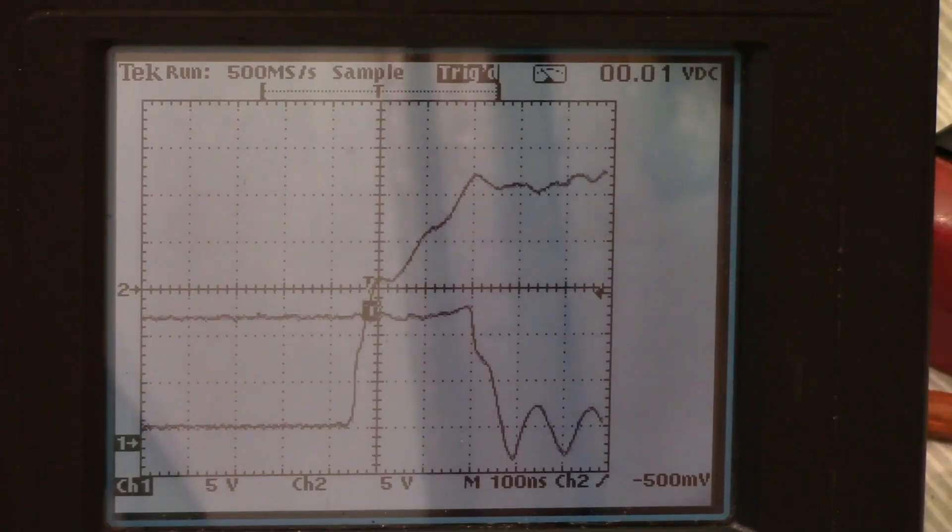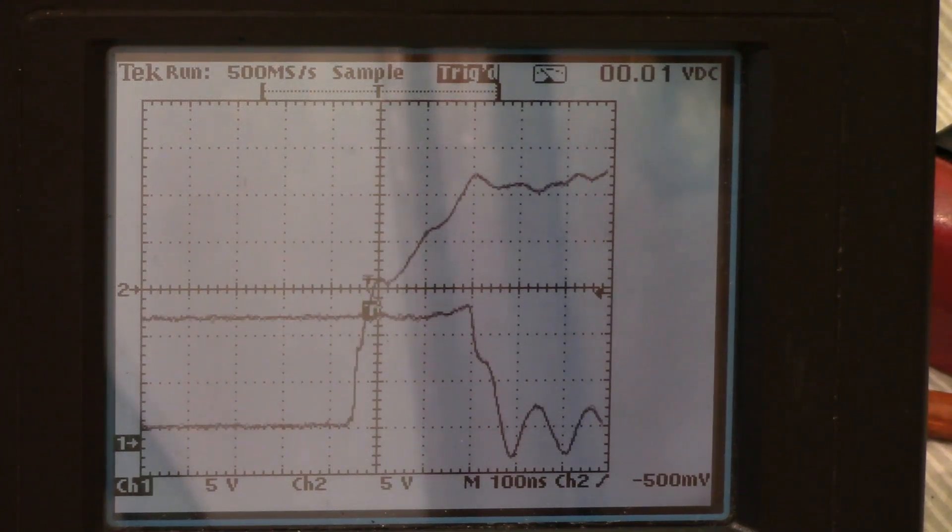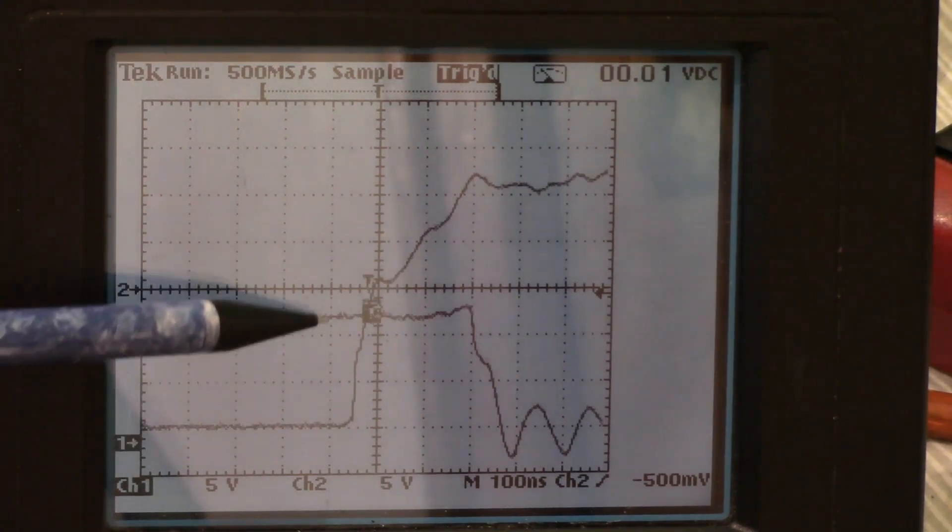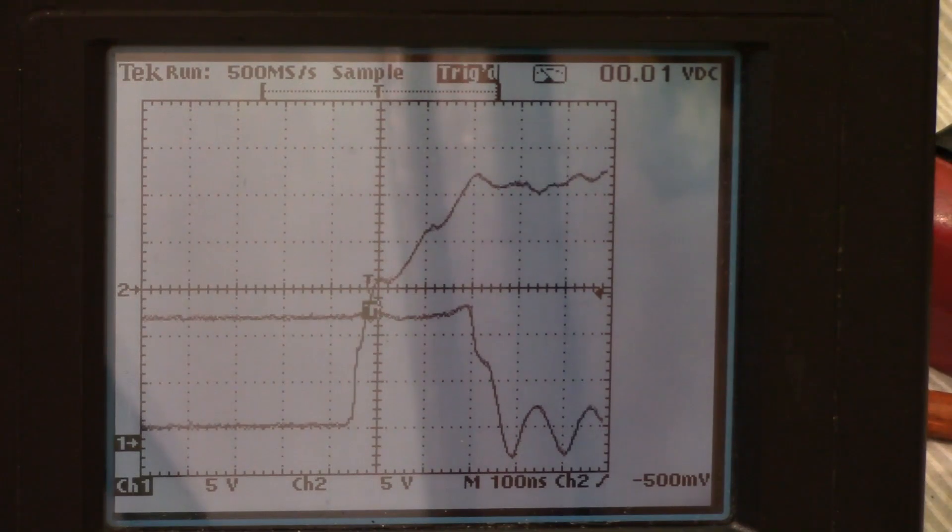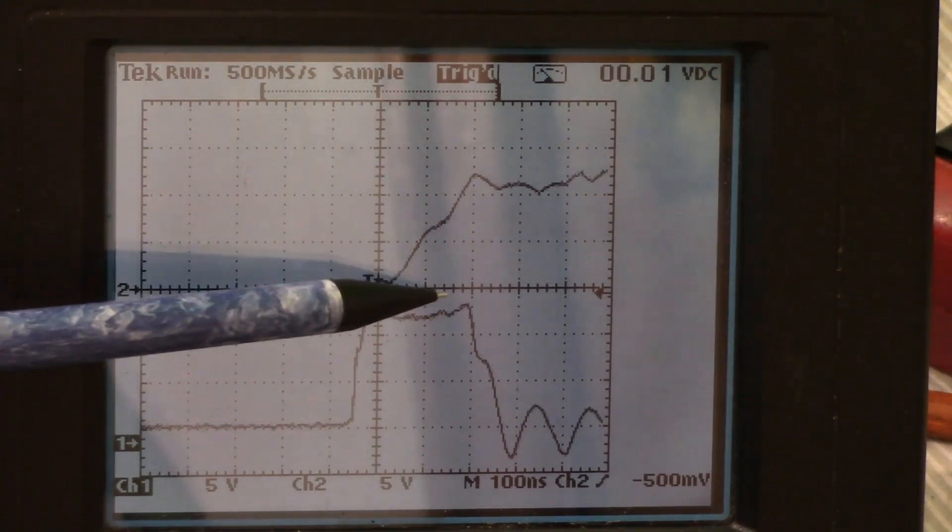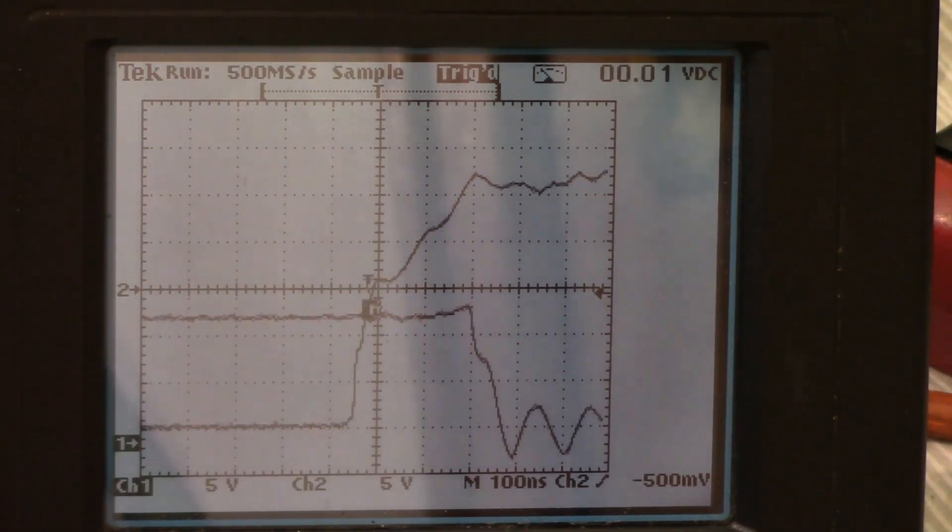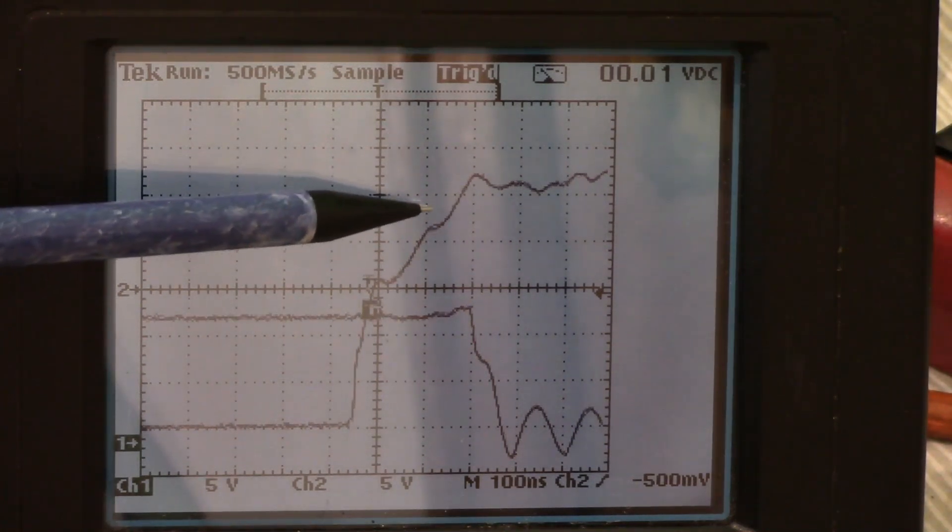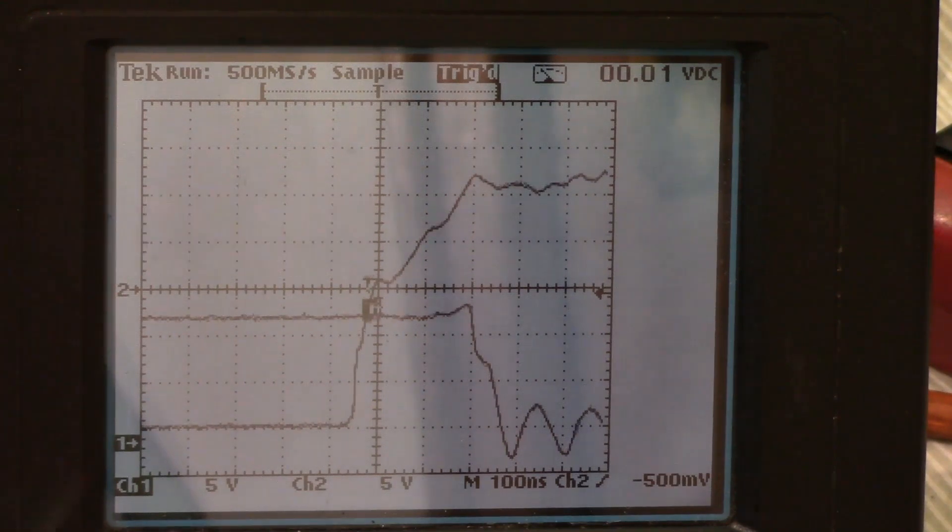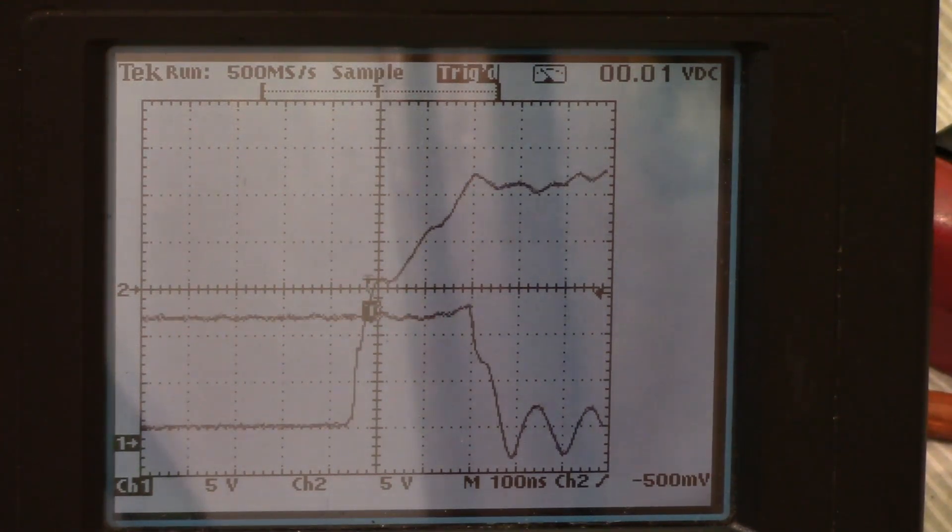Alright, now as you can see, we have two traces that we're scoping here. The first one here, this is the gate voltage waveform, and the other one here is the IGBT at turn on. And you'll notice right here in the gate voltage waveform there's a little knee, and that corresponds to the IGBT threshold voltage.